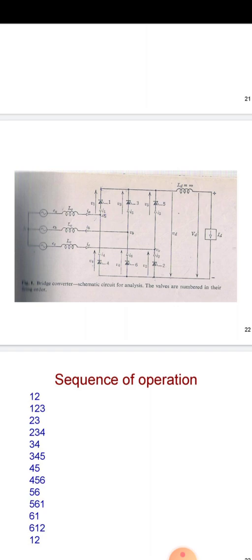The second range, beta between 60 and 90 degrees, gives epsilon equal to gamma minus (beta minus 60). At that time, with increased overlap and consequently earlier ignition of the valve, the dent encroaches on the period in which the valve voltages would otherwise be negative.